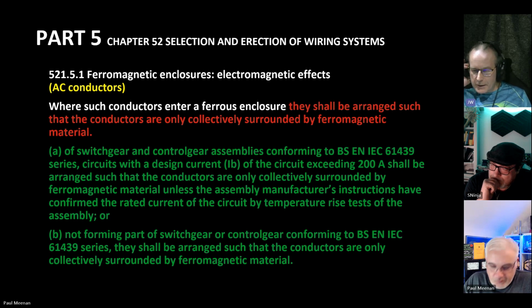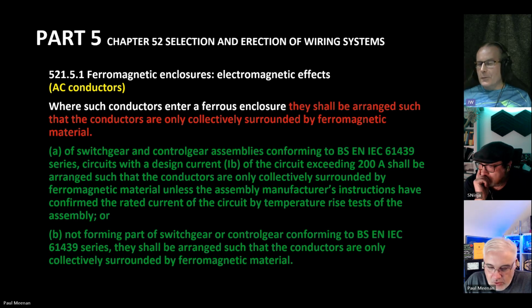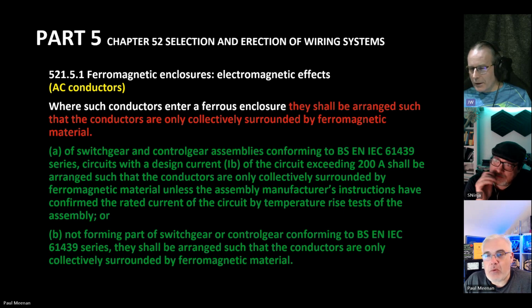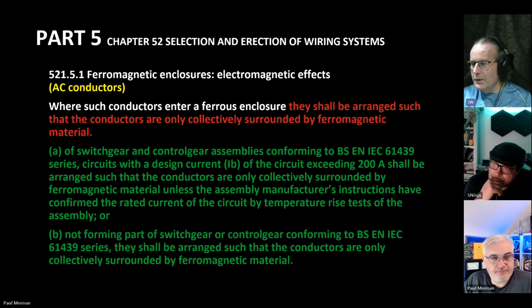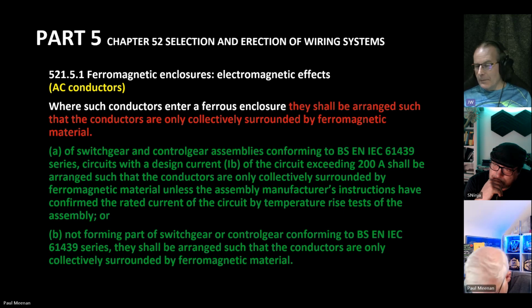However, that part has been deleted. So now it's going to say: where the conductors enter a ferrous enclosure of switchgear and control gear assemblies conforming to BS EN IEC 61439 series, circuits with a design current exceeding 200 amps shall be arranged so the conductors are only collectively surrounded by ferromagnetic material, which is basically the same as we've got, unless the assembly manufacturer's instructions have confirmed the rated current of the circuit by temperature rise tests of the assembly.